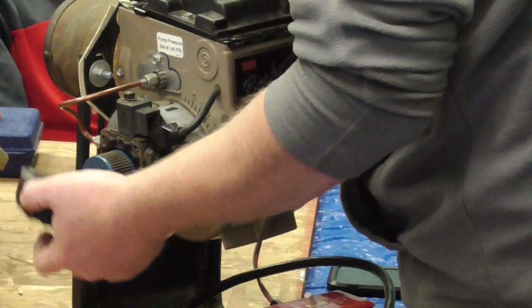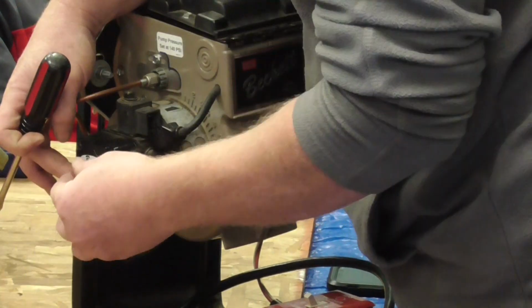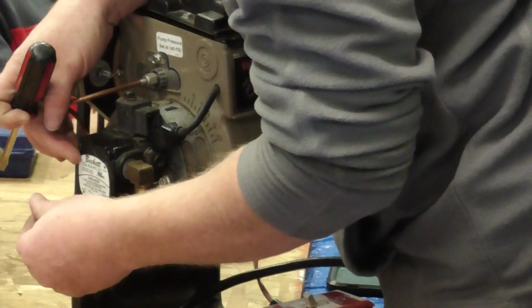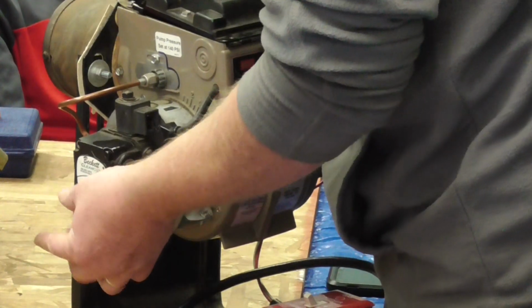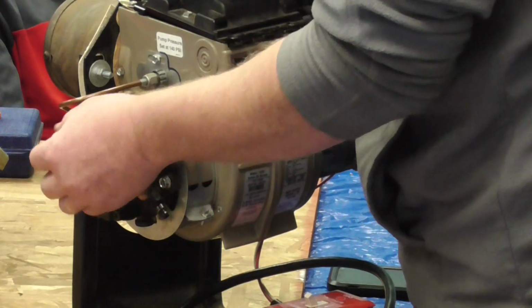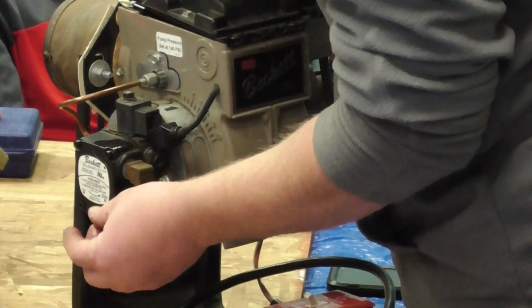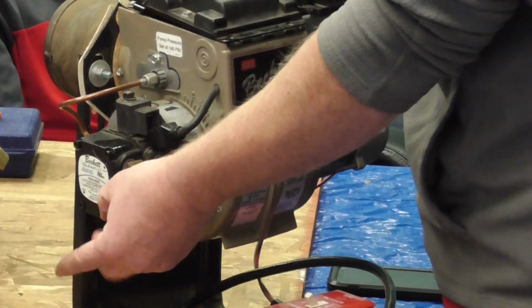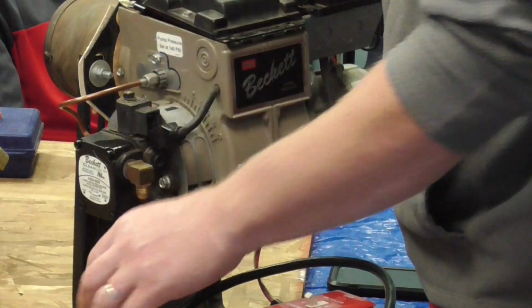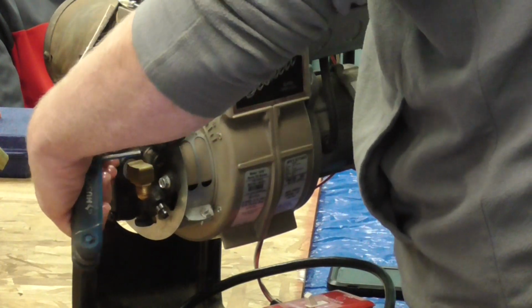Once in a blue moon, usually changing or cleaning that one is more of a diagnostic thing. Like you just can't get flow, or you change the filter and the filter hasn't been changed in forever, or you pull the nozzle out and the back of the nozzle's all cruddy. If the little screen on the back of the nozzle's dirty, then it means everything's been getting past that filter, if there was one. So this filter's probably clogged up too. Not everybody believes in filters for some reason. I do.